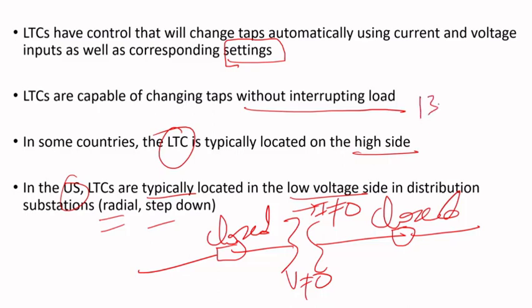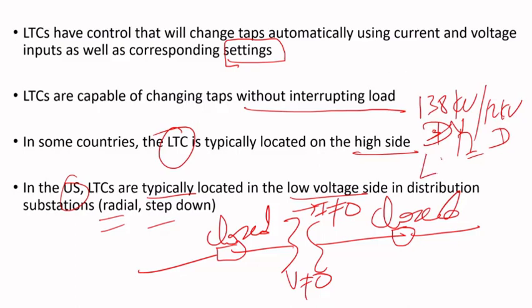For example, with a 138 kV to 12 kV transformer, where one side is delta and the other is grounded Y, it makes sense to put the LTC on the Y side. You can place the tap changer at the neutral point, which requires less insulation and clearance. If you put it on the delta side at 34 or 69 kV, it requires a lot of insulation clearance — phase to phase, phase to ground, tap to tap — making the tap changer physically huge.